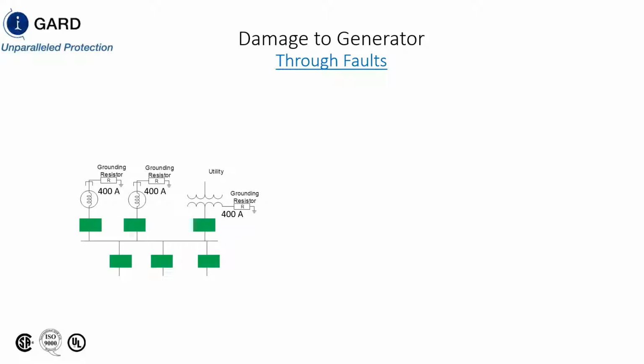If you have a through fault, let's say for example you have 3 sources in this particular example. You have the generator, 2 generators, and engineers like to duplicate things. So if you have one 400 amp low resistance grounding system and you put in another generator, chances are it's going to be a 400 amp 10-second resistor. And the utility is going to be a 400 amp 10-second resistor. So if you have a through fault, and a through fault is going to be a fault somewhere in the facility, if all 3 sources are operational, then you're going to have 1200 amps of available fault current because all 3 sources are in parallel. And we'll talk more about this later. The breaker closest to the fault will trip.